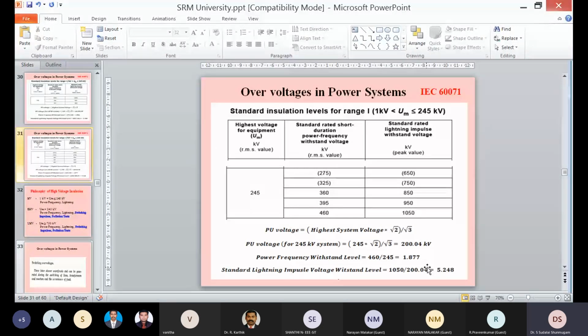It literally means if I have a system of 245 kV, I repeat, my system voltage is 245 kV, then the insulator I am using in the system should be able to withstand 1050 kV of lightning impulse voltage and 460 kV of power frequency voltage.